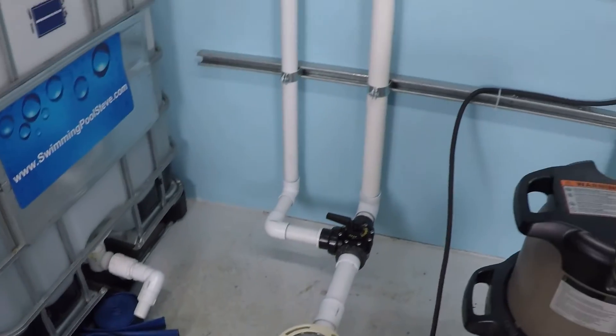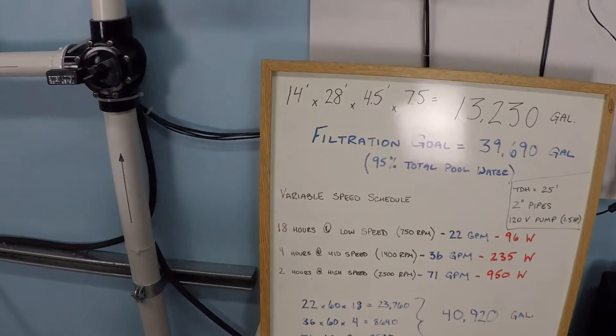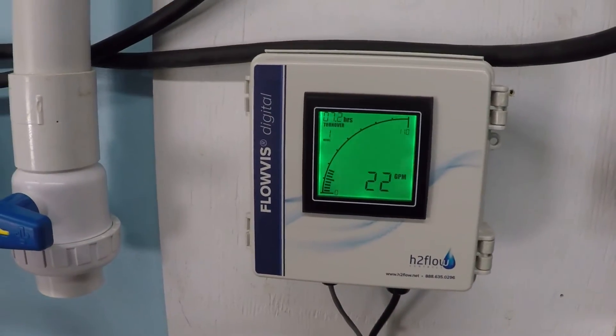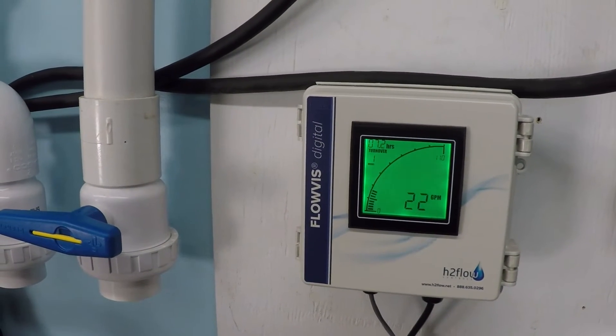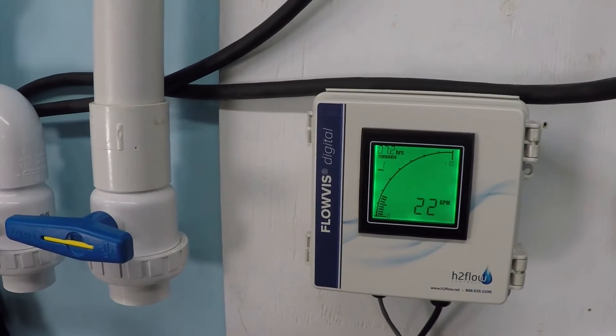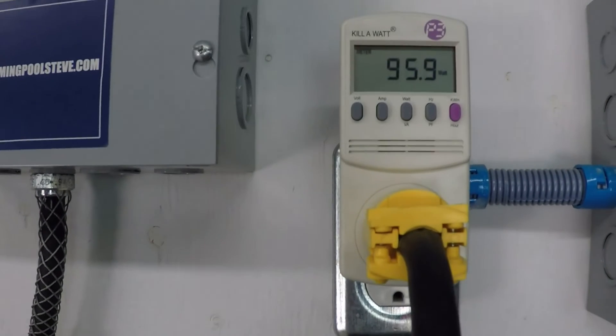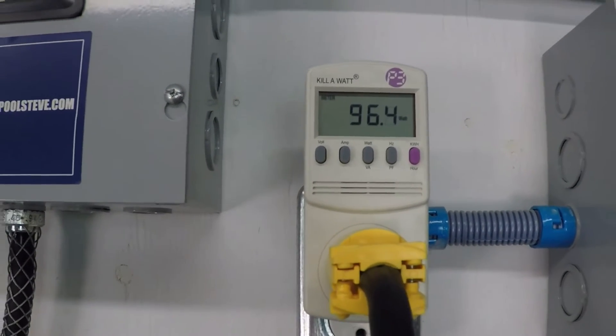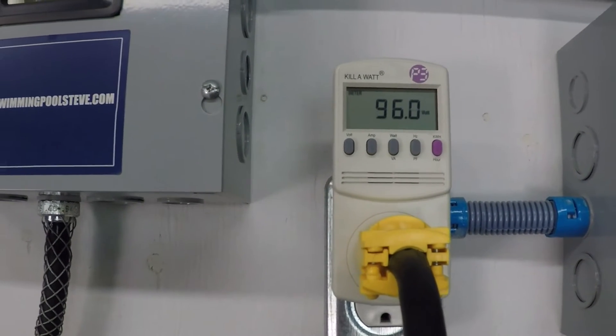750 RPM on this system, which again has a TDH of about 25 feet, is resulting in 22 gallons per minute. 750 RPM is extremely low, but 22 gallons per minute is actually a pretty appreciable number. Especially when you look at the fact that it costs less, in terms of power consumption that is, less than a 100 watt light bulb.